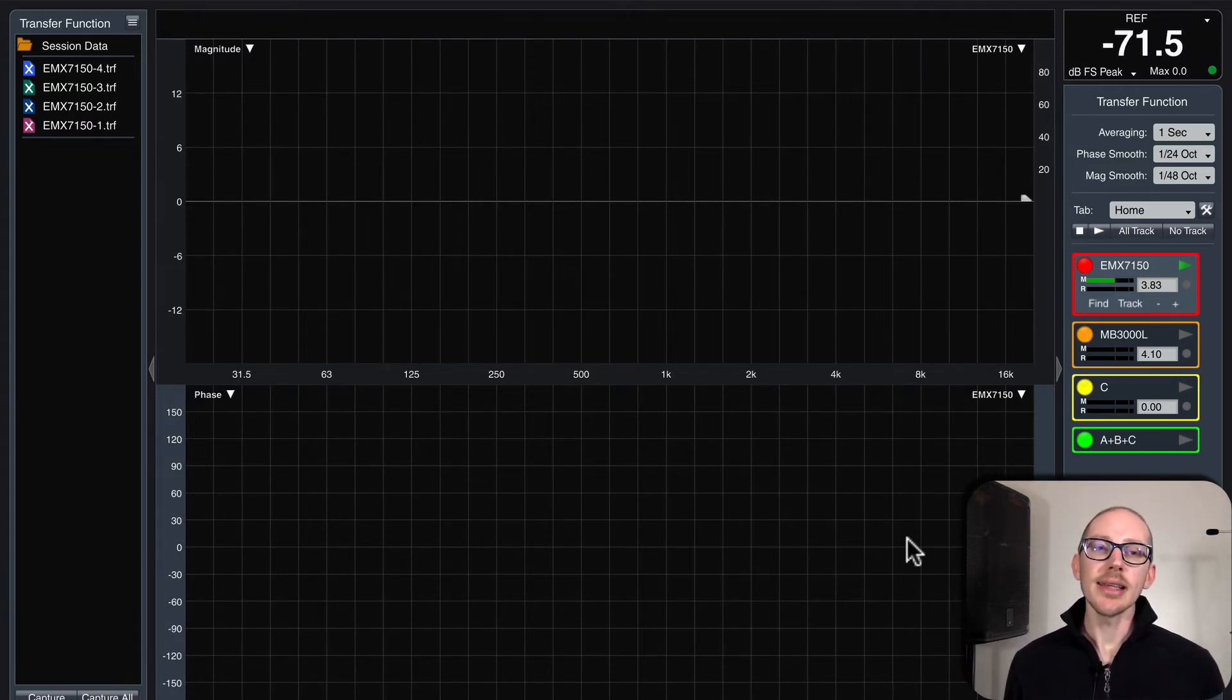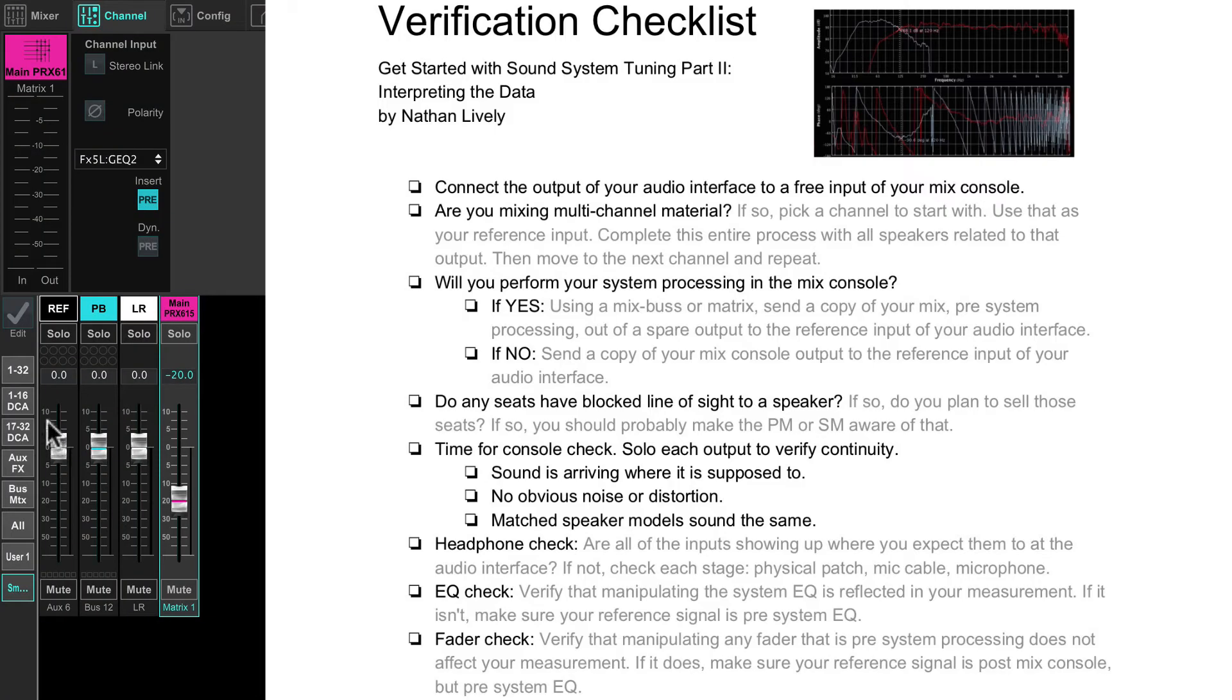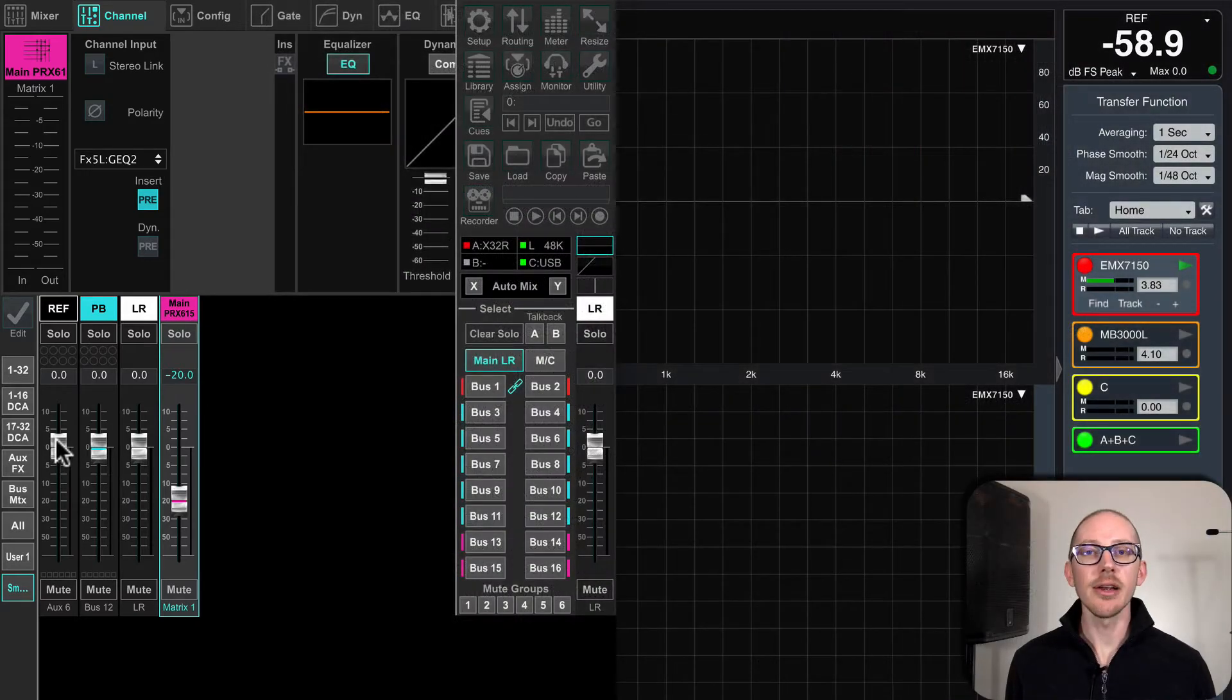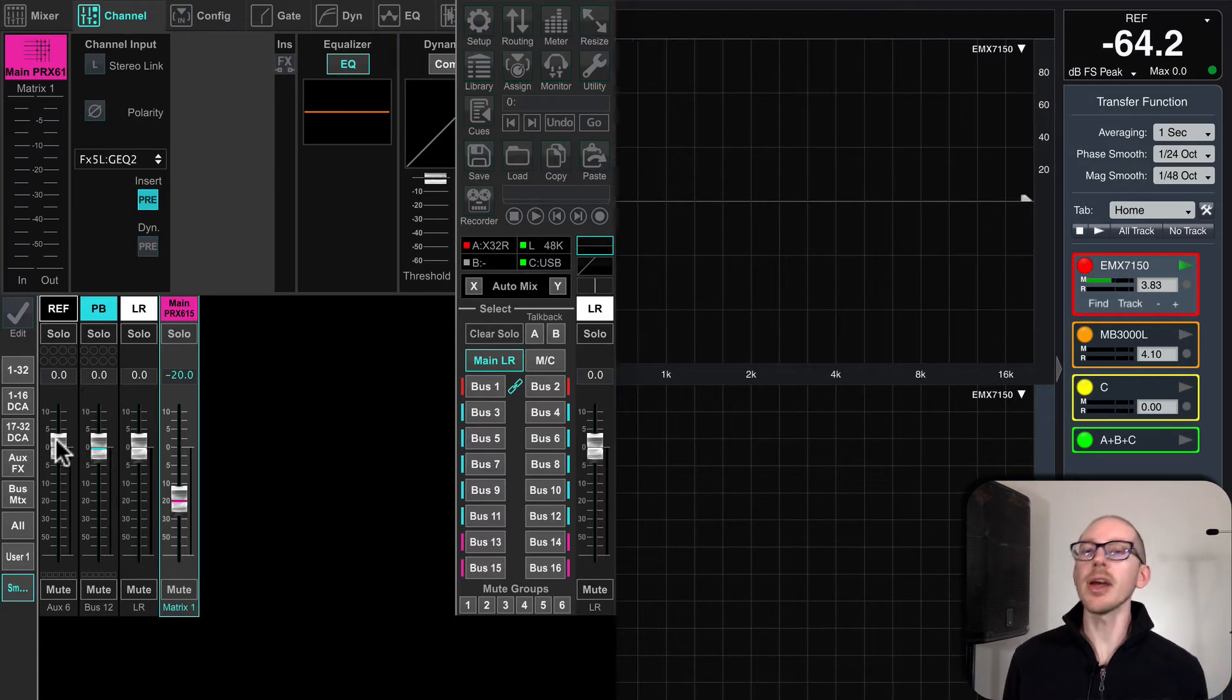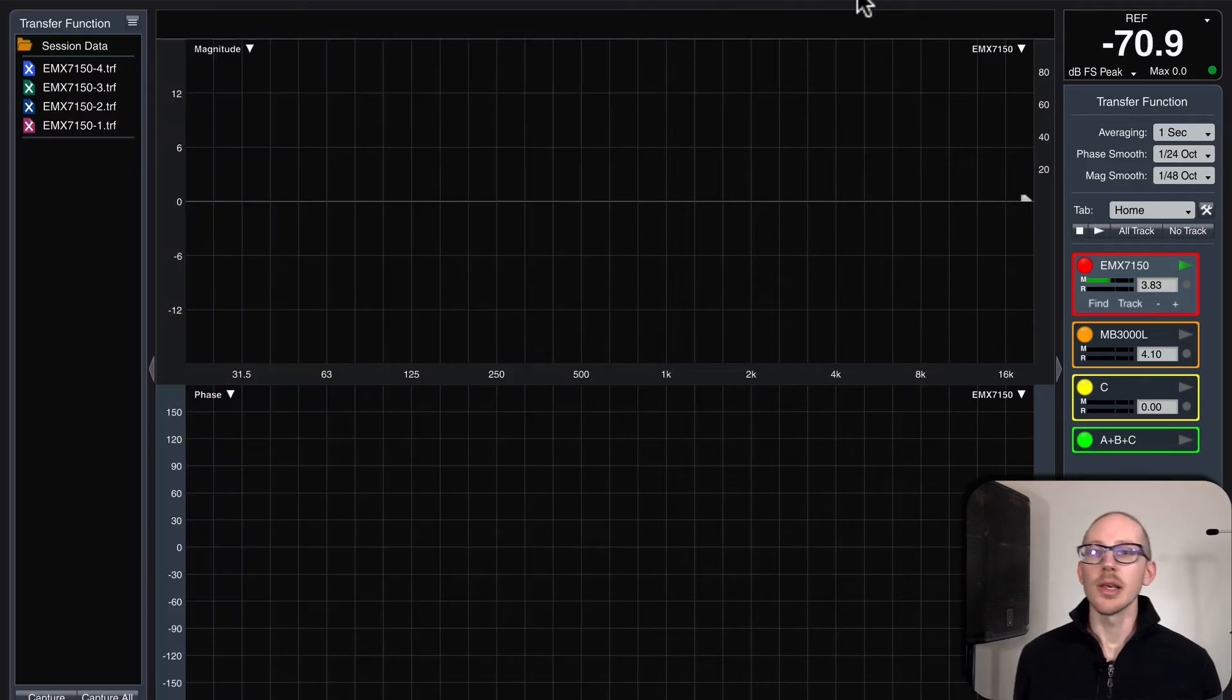So this is a step in the audio analyzer verification checklist that I call the fader test, and it's simply that I should be able to move up and down my reference signal fader to put more sound into the room, put more sound into the system, into the device under test if I need to, without changing the trace here. Let me show you what I mean.